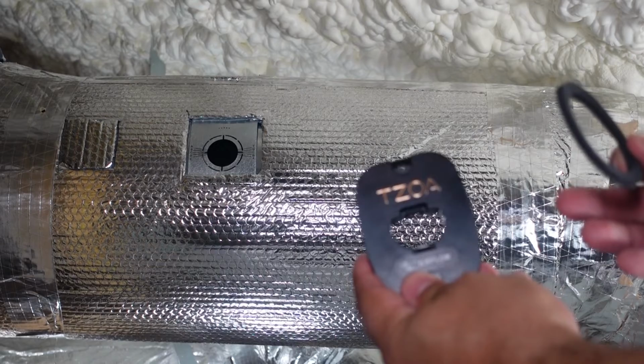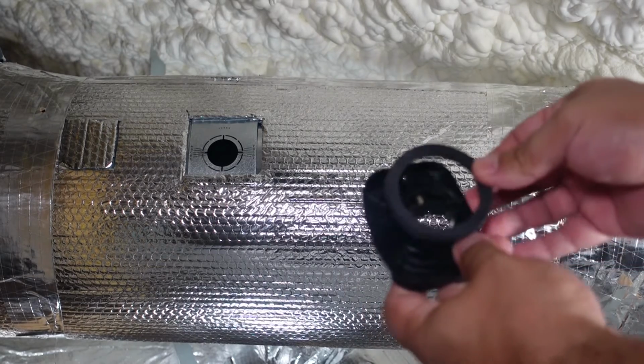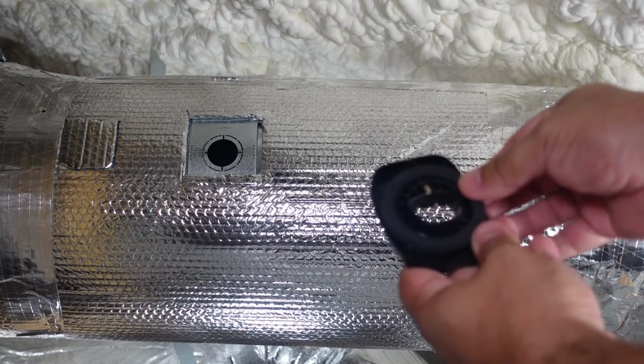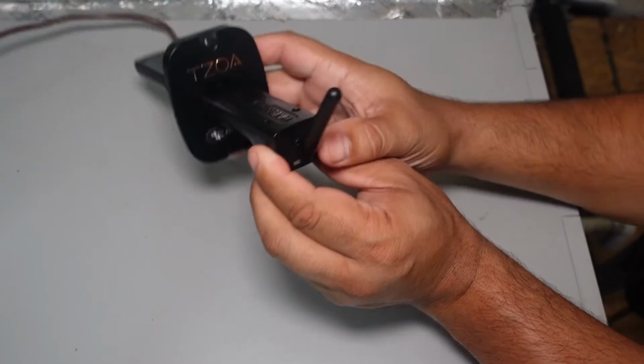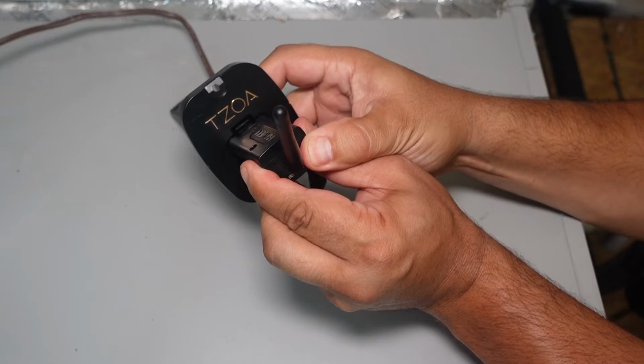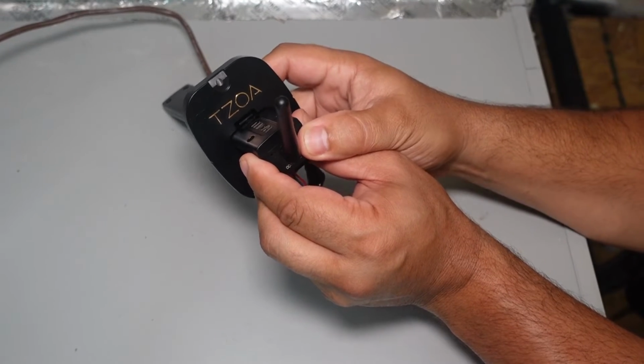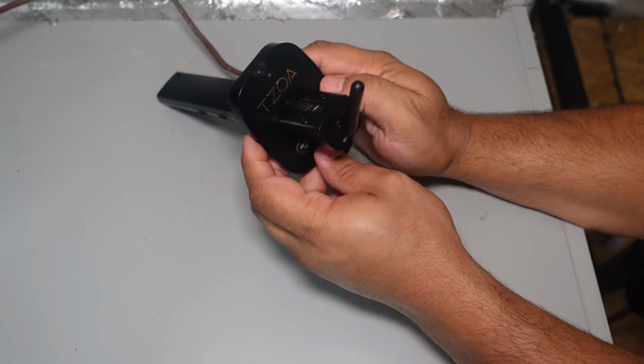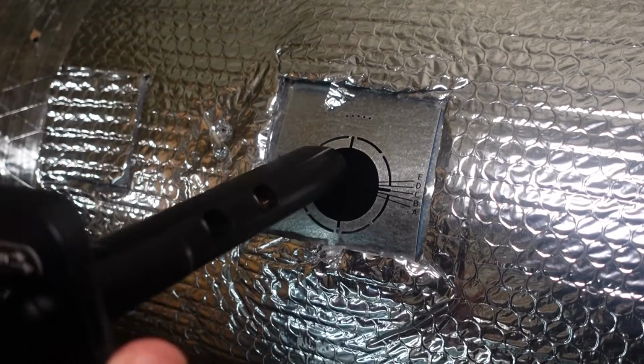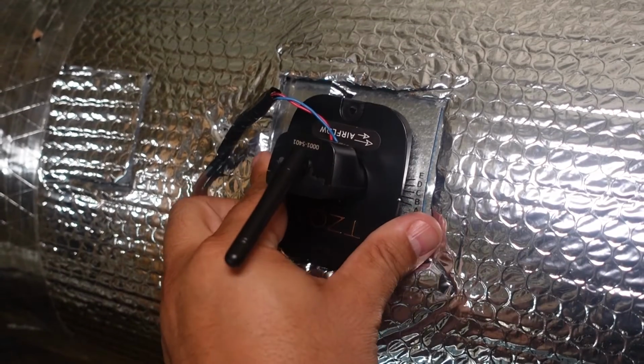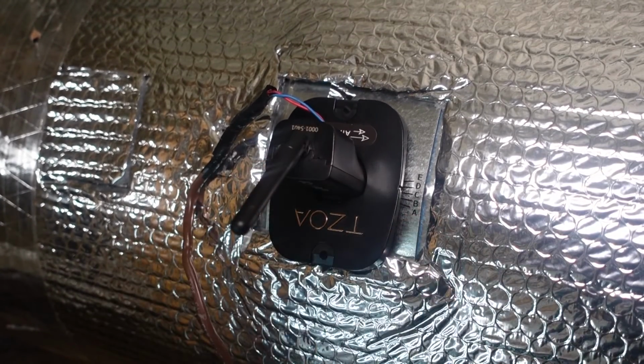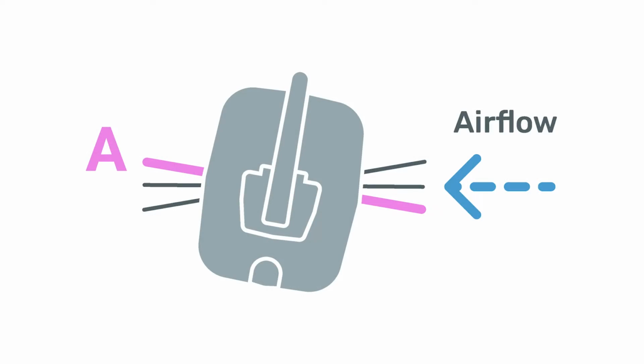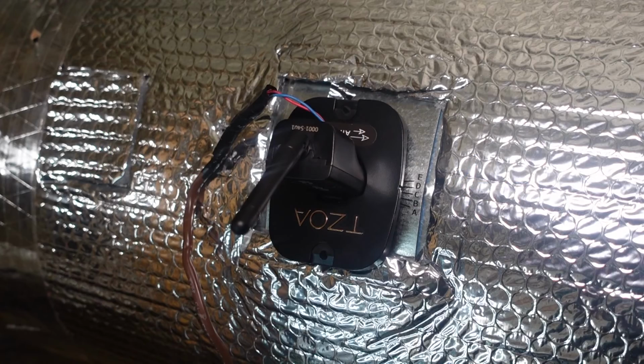Grab the plastic mounting plate from the box and apply the small gasket for flat ductwork or the large gasket for round ductwork. Insert the monitor probe into the mounting plate until you hear a faint click. This ensures that the particle sensor will activate once connected. Now, gently place the monitor into the hole in the duct and loosely position it so that the arrows point in the direction of airflow. Do not secure the screws at this point.